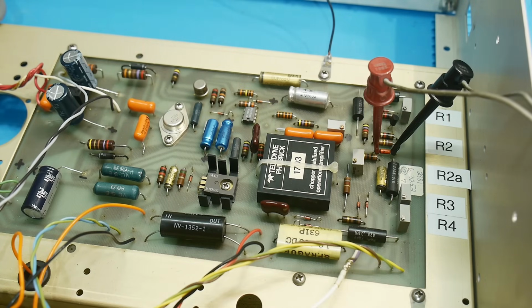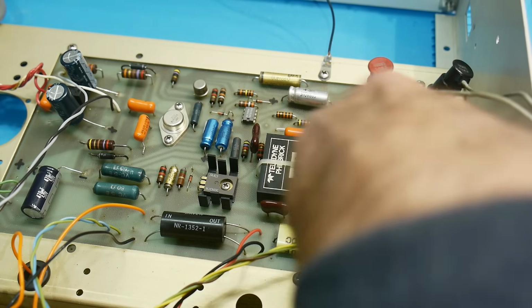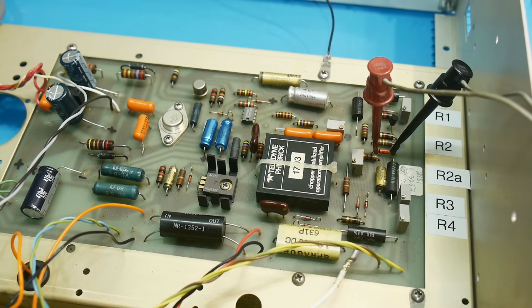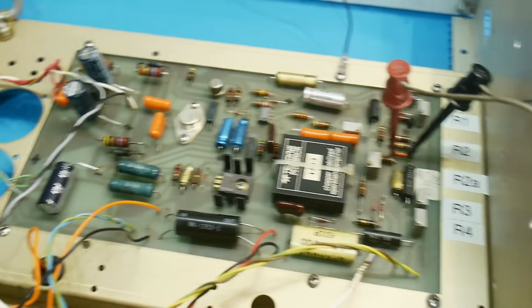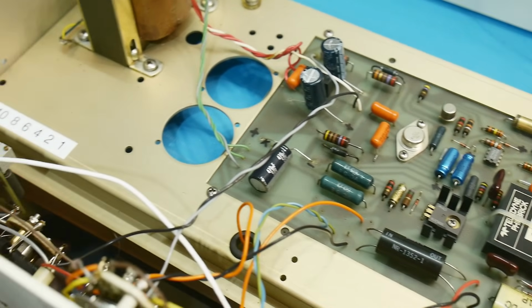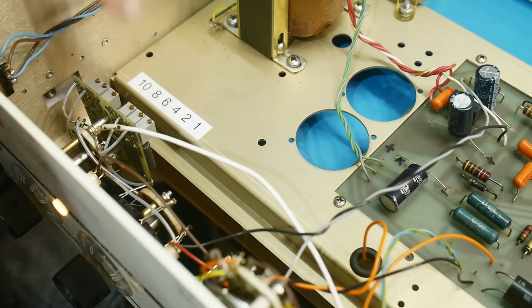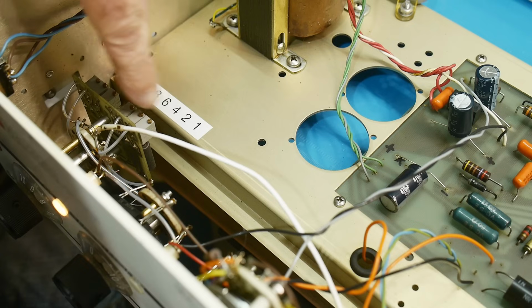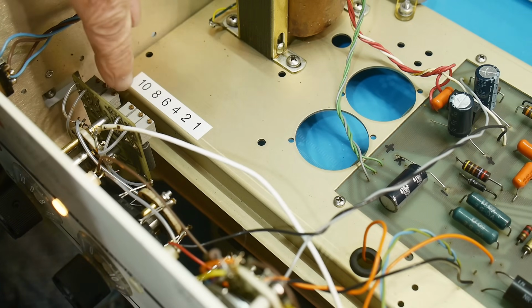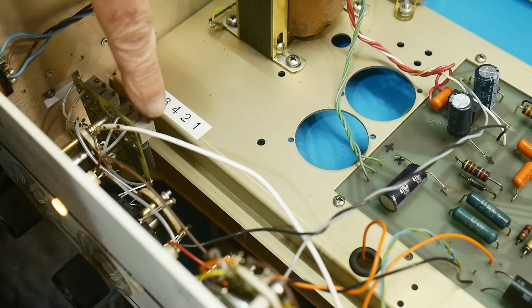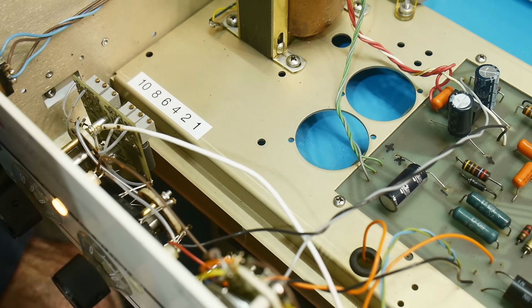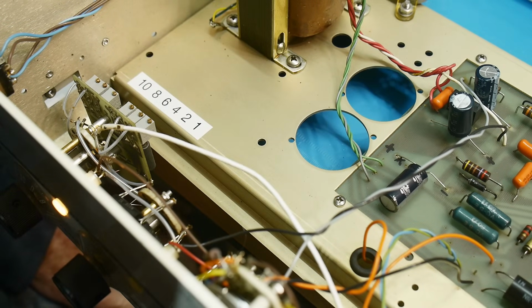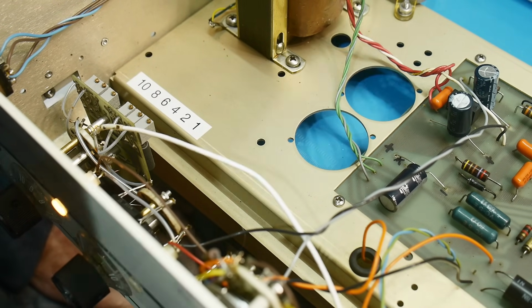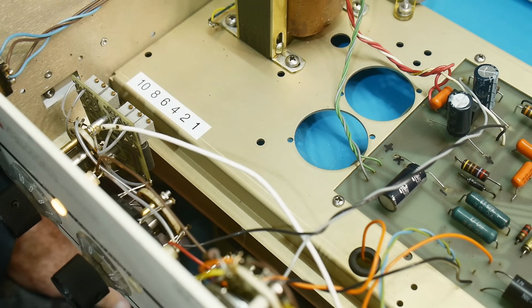Like I said, in order to calibrate this thing, you adjust this for a particular range, and then you need to calibrate another thing, which is not on camera. There we go. There are these adjustments right here for 1 volt, 2 volts, 4 volts, 6 volts, 8 volts, and 10 volts. And each one has a separate adjustment, so you have to go through all of that. So let's see how we're doing here. Let's move things around a bit.